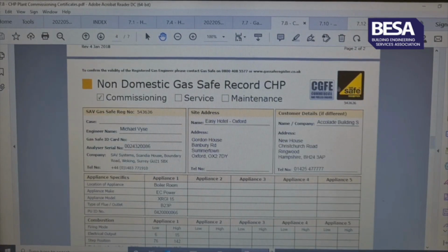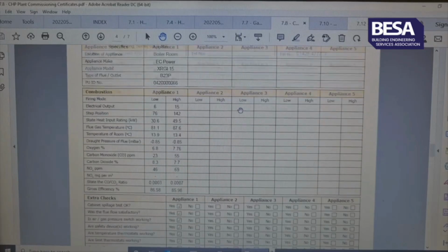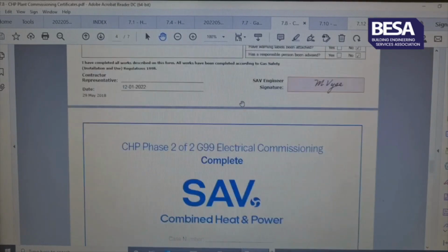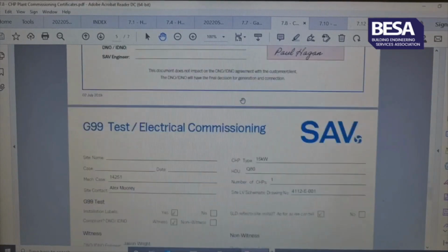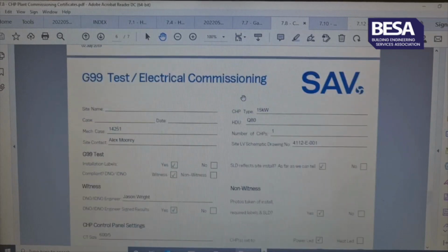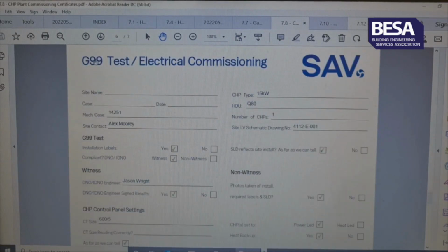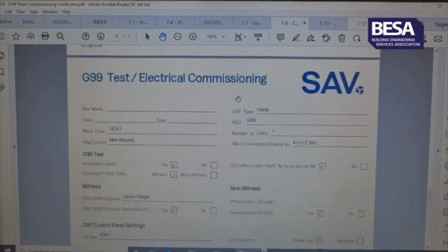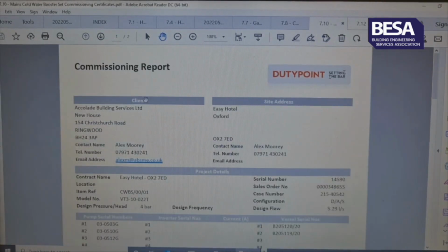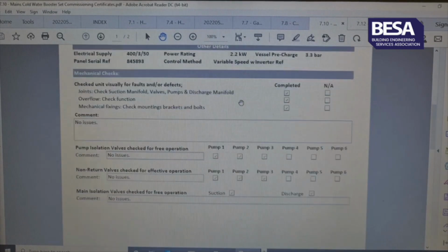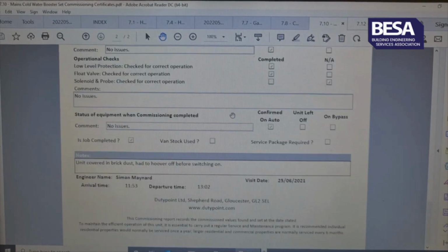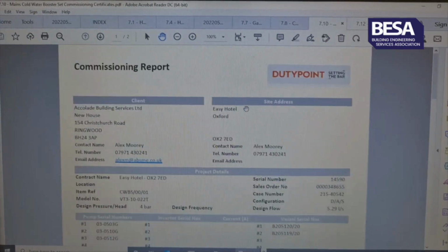They're Gas Safe registered as well. They carried out a gas purge on the CHP machine. The G99, there you go, that's what I was looking for. The G99 is included in there as well, that's all signed off. Next test I've got, this is the commission report for the cold water booster set, manufactured by a company called Duty Point, and they commissioned the set themselves. Again, no problems, all signed off.